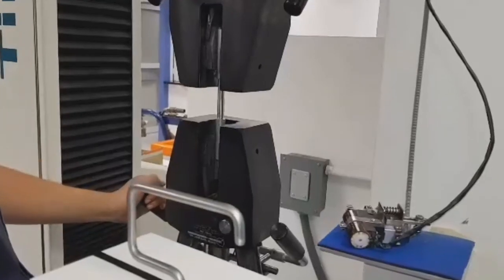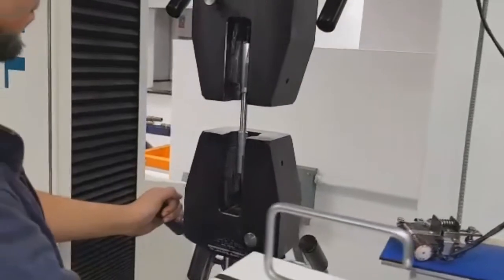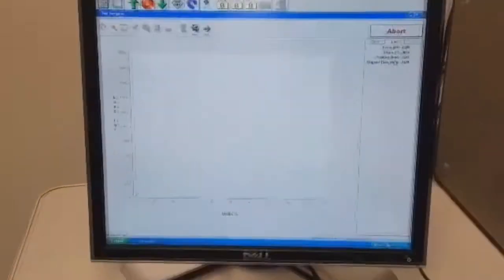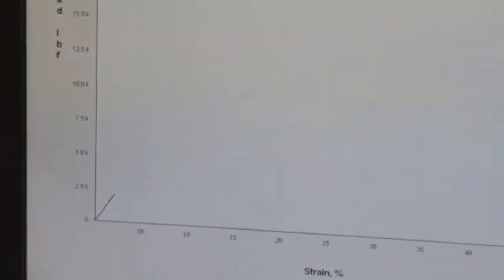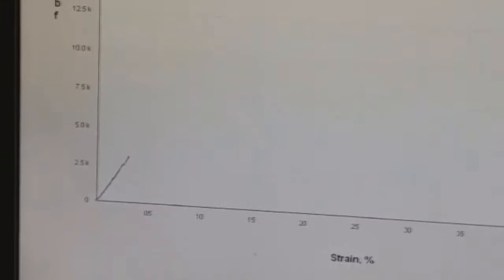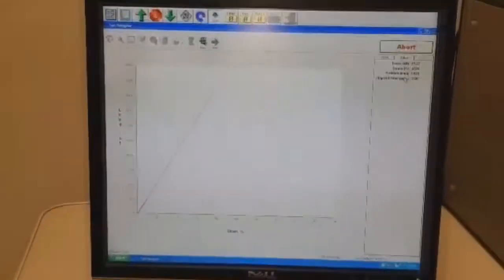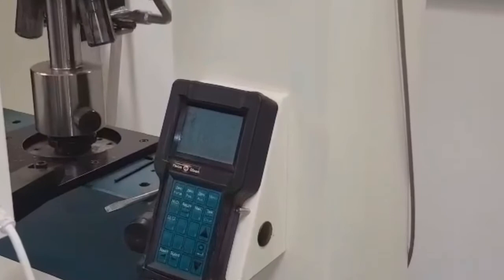H300KU after checking all the calibrations of the machine. To calibrate this machine, we need to compare the patterns from the load cell with a specific calibration sheet. This process is commonly done by the producer of these machines. Finally, we compare the results obtained from the machine with the theoretical equations in order to obtain a certain percentage error. Note that if the percentage error is less than 10%, it will be acceptable. Otherwise, the user must assume that the calibrations of the machine were not done correctly, producing in this way a high margin of error.